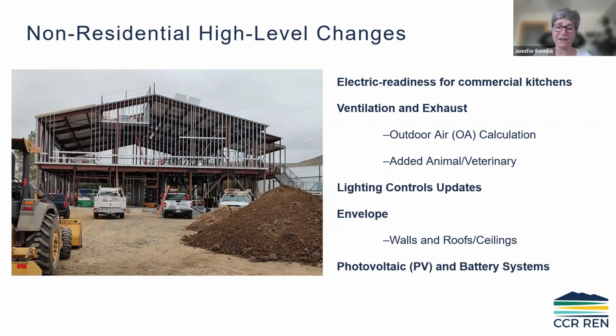So to all the architects and plans examiners, you should take a look at that and have the designer put on their drawing that they did that measurement to meet the point of use, because it also has to do with your piping size. Depending on if it's 1/2 inch or 3/8 inch diameter piping, it's also going to dictate the distance. We won't get into it in this particular slide deck because we were just trying to hit a whole bunch of topics, but it's in there, and we'd be happy to work with you on a Code Coach question for that.